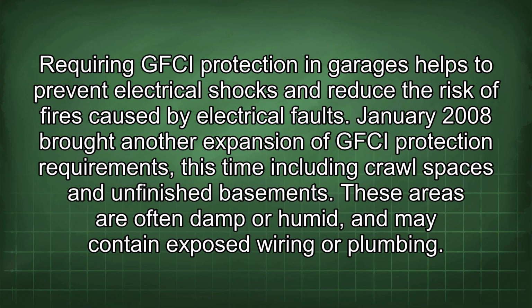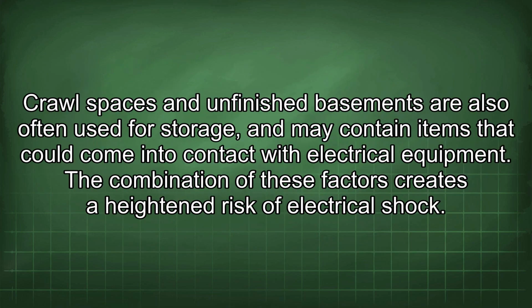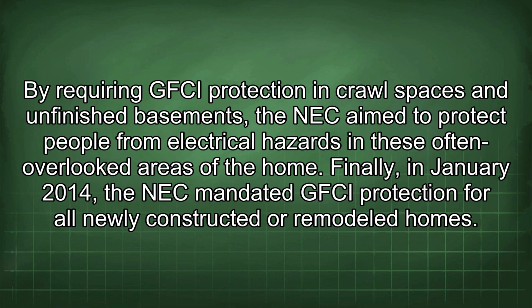January 2008 brought another expansion of GFCI protection requirements, this time including crawl spaces and unfinished basements. These areas are often damp or humid, and may contain exposed wiring or plumbing. Crawl spaces and unfinished basements are also often used for storage and may contain items that could come into contact with electrical equipment. The combination of these factors creates a heightened risk of electrical shock. By requiring GFCI protection in crawl spaces and unfinished basements, the NEC aimed to protect people from electrical hazards in these often overlooked areas of the home.